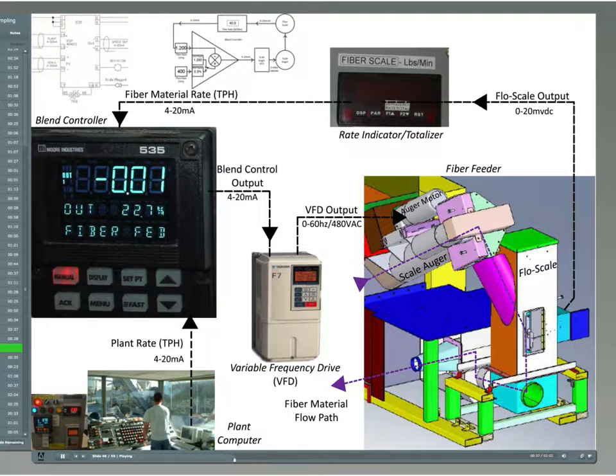To configure the controller unique to this application, the following parameters are required to be set as such. Remote set point, type 4 to 20 mA from plant rate output, is enabled to recognize the plant tons per hour. PV type, 4 to 20 mA from the flow scale is enabled. Contact 1 shall force the 535 to manual when fiber feeder is shut down. This allows the controller to remember what speed scale auger is to run at when the feeder is restarted in automatic. Consequently, this reduces a lengthy ramping up time and overshoot when the process is restarted at a rate the process was at before shutdown.